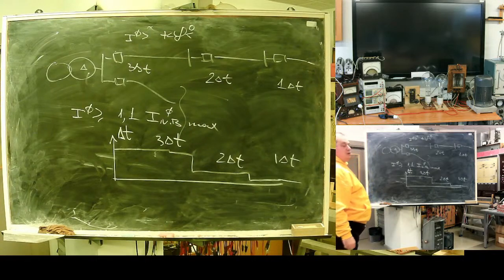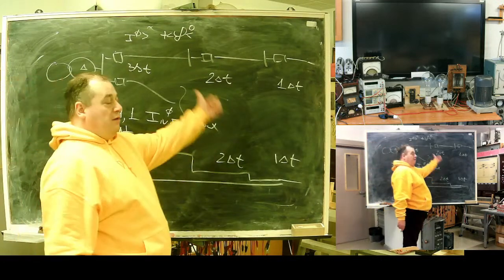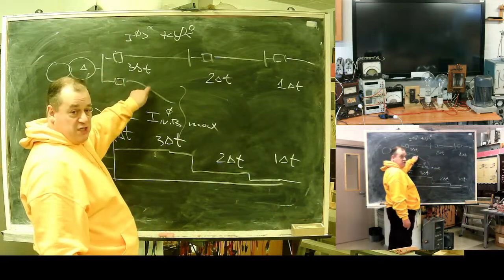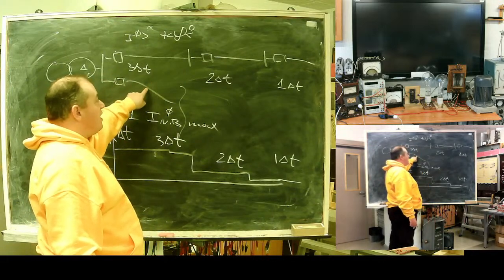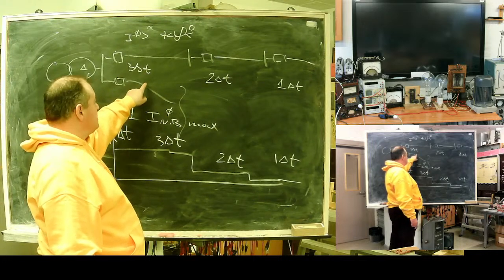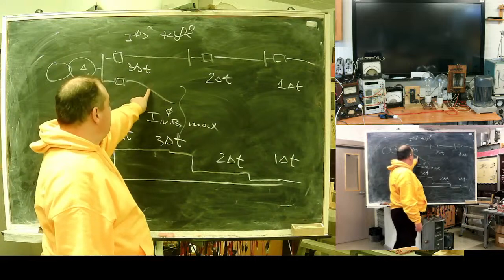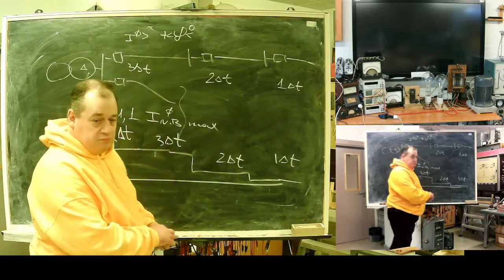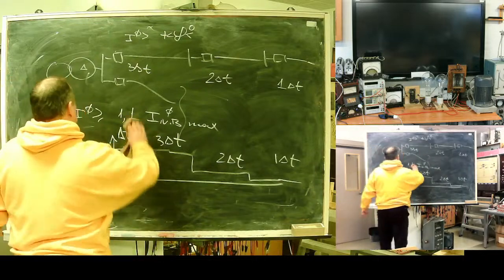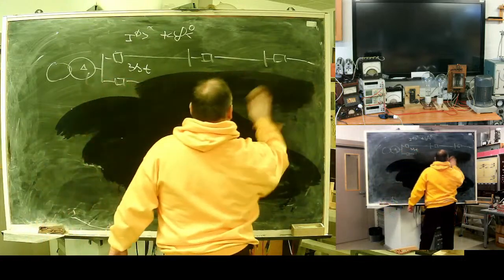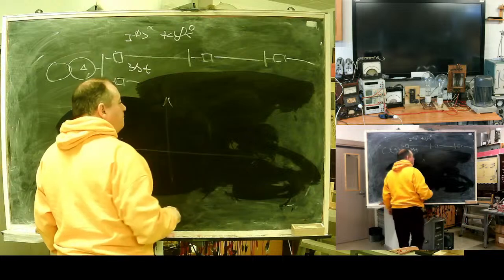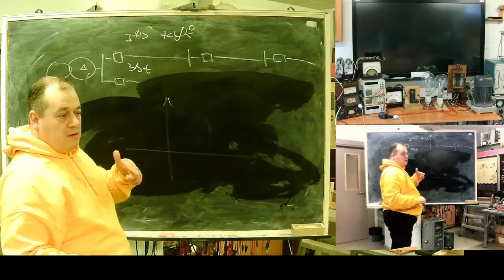Now, what about direction? What do we need? We need to prevent backward operation. We need to prevent operation in case the fault is here. We will see current. Again, zero sequence current is determined by the healthy part of the network. So there will be a current here. We need this protection to be polarized. What will we see? We will see a capacitance.